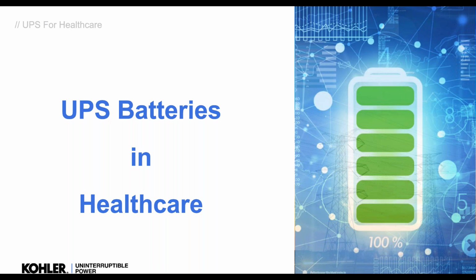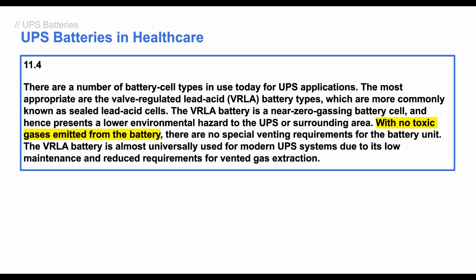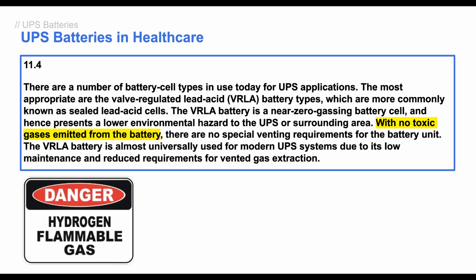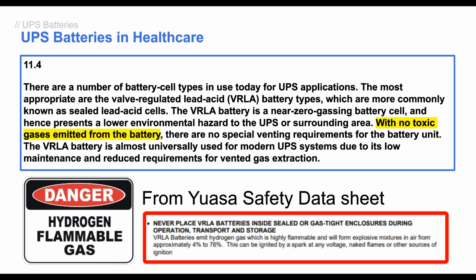So, batteries in healthcare, there are some requirements in HTM. It talks about non-toxic gases emitted from battery. There are no special ventilation required. Batteries, although it's not toxic, hydrogen is emitted from the batteries, and we do have to vent it as required. Okay, so there are venting requirements. You cannot put a battery in a sealed room, in a sealed place.